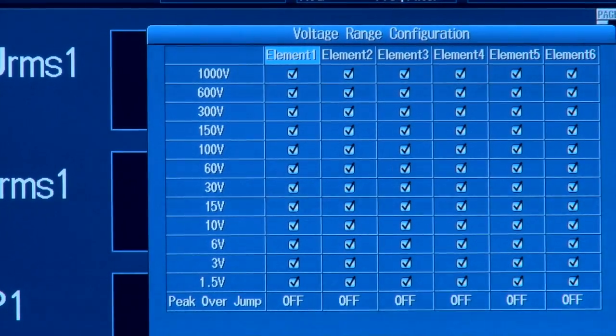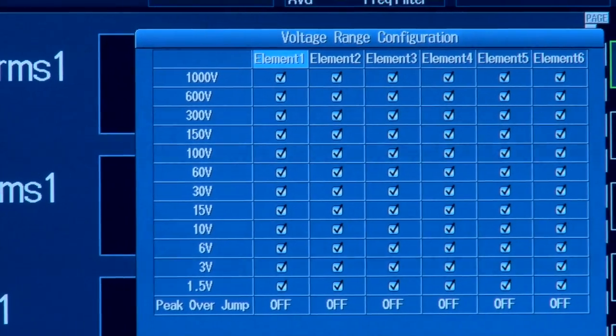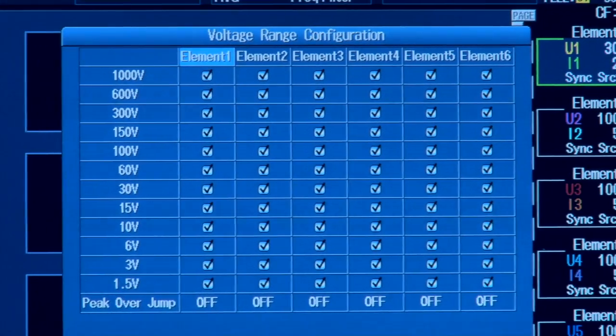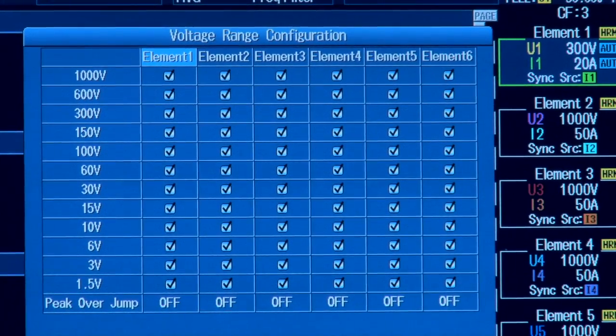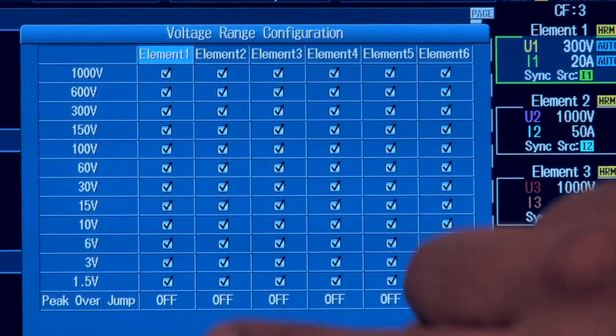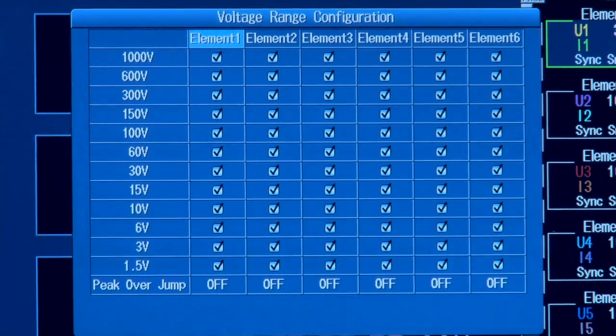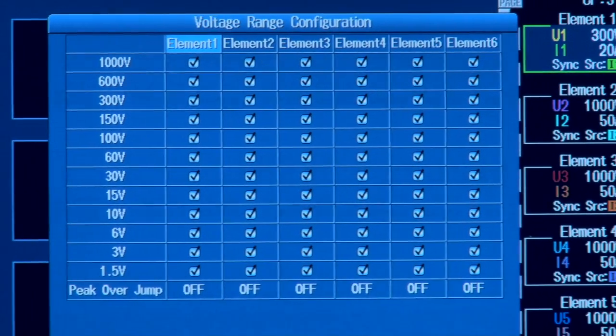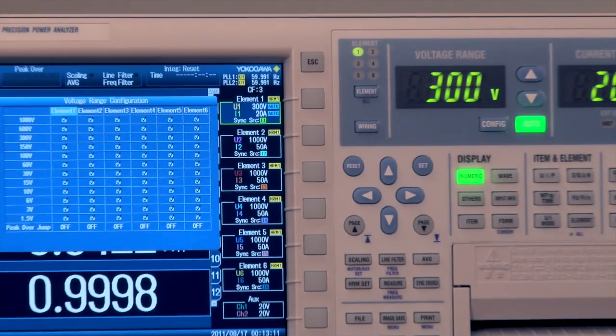By deselecting unwanted ranges you minimize the amount of time it takes for this unit to stabilize through the ranges and start making effective measurements. If you're doing repetitive testing from zero to say 600 volts, you can take out any of the unwanted ranges, therefore it would go from zero to 600 volt range and then your measurements would be ready to go.